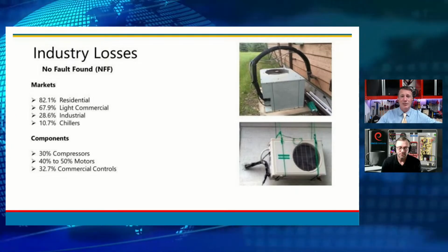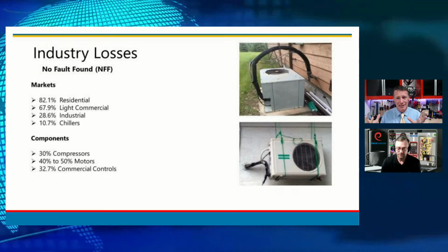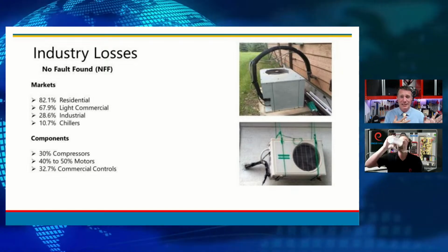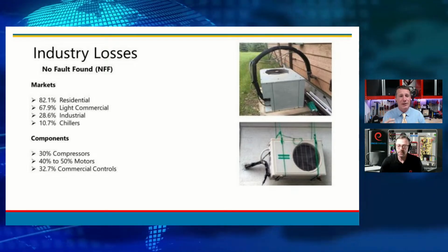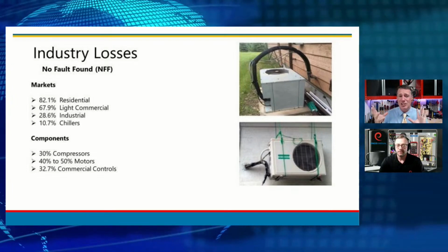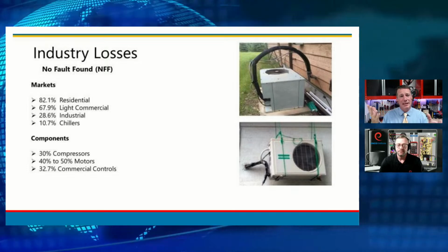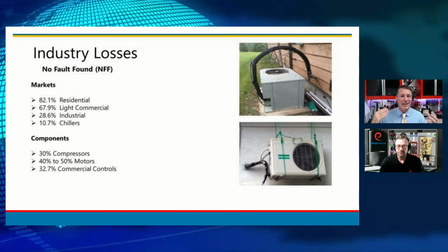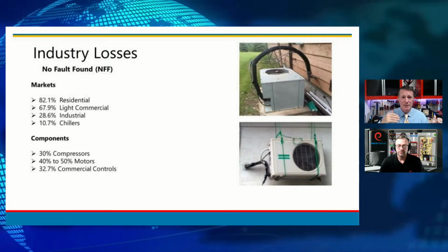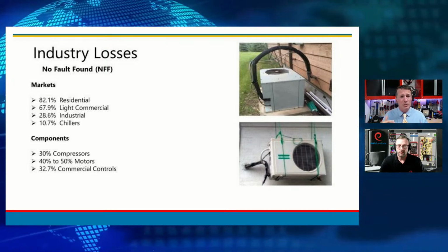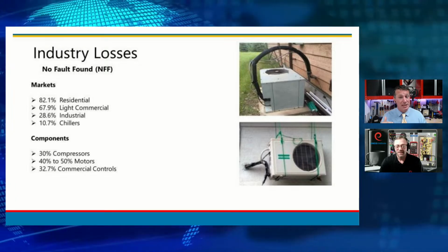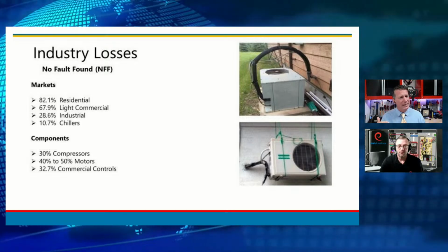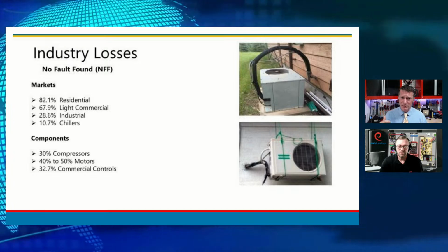A big reason that we're here is to help you understand. If we're not educated, we end up with byproducts of a lack of education. One of the studies we did, a few years ago, looked at replacement parts for equipment: how does education affect replacement parts? We looked at the entire spectrum of the HVAC industry. In residential markets, about 82% of the parts coming back under warranty from technicians in the field showed no fault found. That's a lot of misdiagnosed parts. Pretty extreme. Commercial was 68%, industrial 28%, and even on chillers it was very low, only 10%.